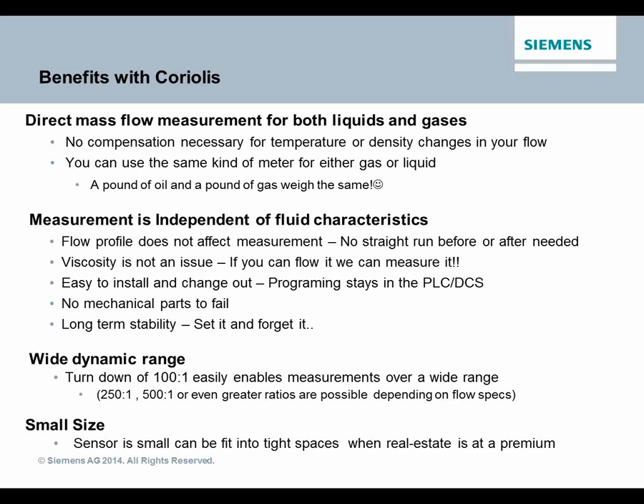There are no internal mechanical parts to fail. It's basically a pipe, and the vibration that the pipe does is extremely small. The devices, once installed, are very stable long term. Once you zero the meter and the parameters don't change, it's pretty much a set and forget it.